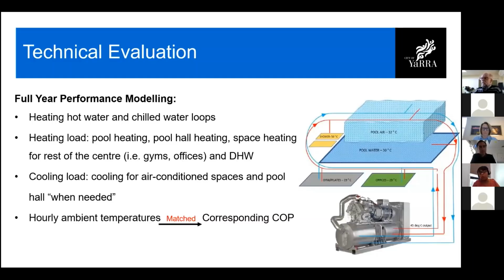So for the heating load, we calculated the heating load needed for pool heating, pool hall heating, space heating for the rest of the center, everywhere that is air conditioned, and the domestic hot water load. Then for the cooling load, it was cooling for air conditioned spaces, but also pool hall when needed. And as Alan explained earlier, although we need to heat our pool hall most of the year here, we do have those days when the outside air temperature exceeds 28-30 degrees, which is the ideal temperature for a pool hall environment.